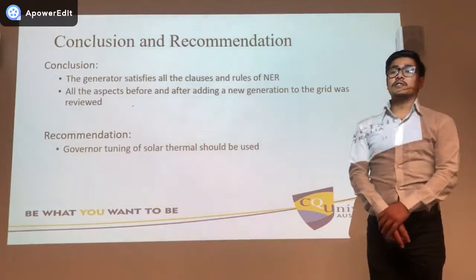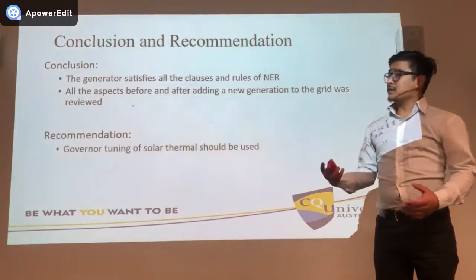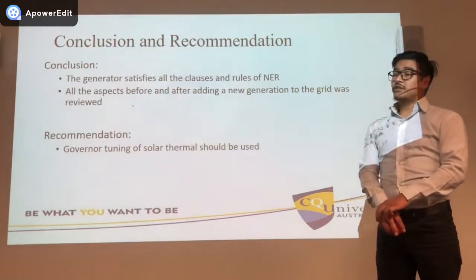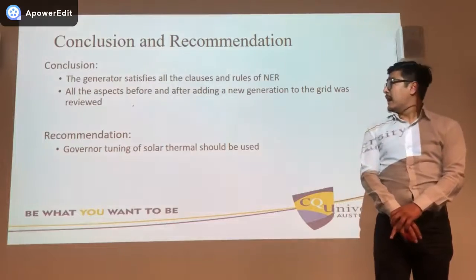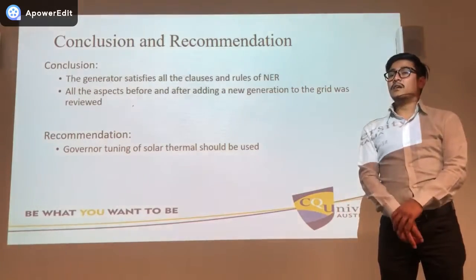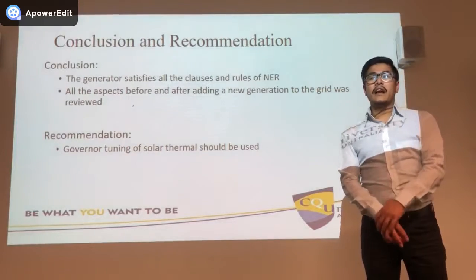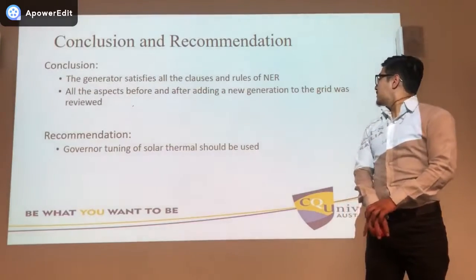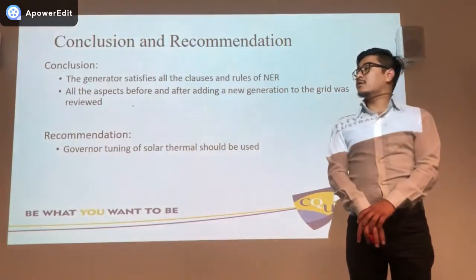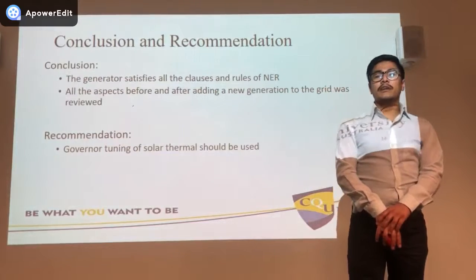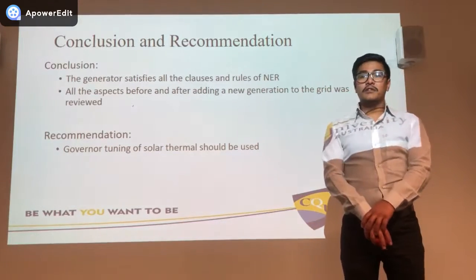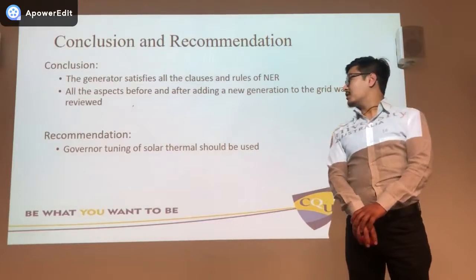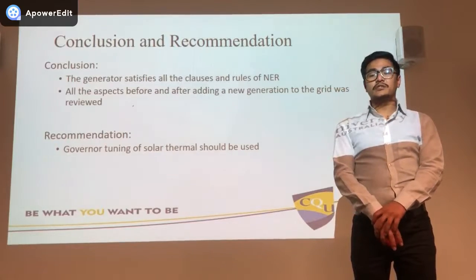As a conclusion of the project, the generator that we planned satisfied all the clauses and rules of the national electricity rules, and all the aspects before and after the addition of the new generation to the grid system were also reviewed. As a recommendation, we were unable to tune the governor of the generator, so it would be better if the governor of the generator could be tuned finely.